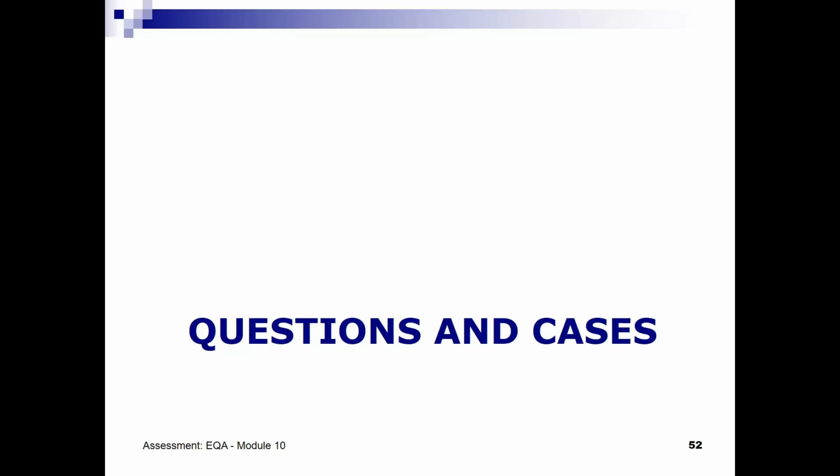That's number one. And number two, one thing you can do, and I have done: at Johns Hopkins Bayview, one time we had a terrible problem with our phosphate. We failed like 5 out of 5. But we went and fixed that, and we didn't want to wait another 3-4 months before starting testing. You can actually contact the accrediting agencies, whether it's CAP or UK NEQAS or SANAS or whoever. A lot of times they will be willing or able to send you another batch of materials out of cycle, so you can get started. So that's one idea.